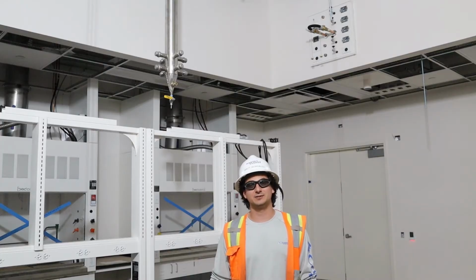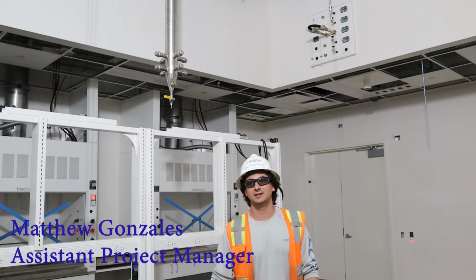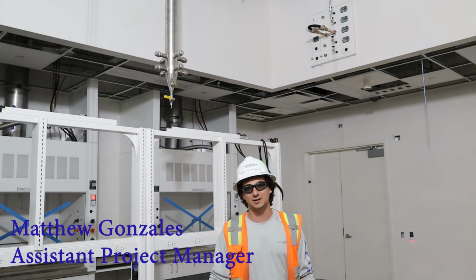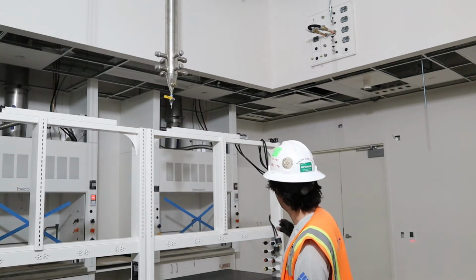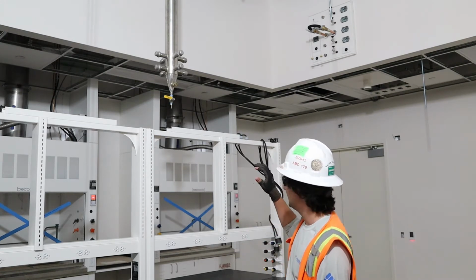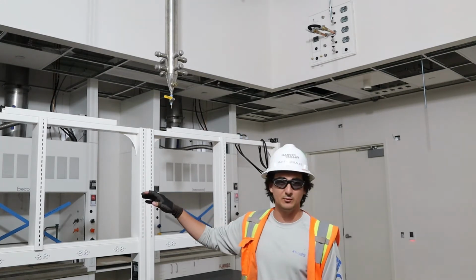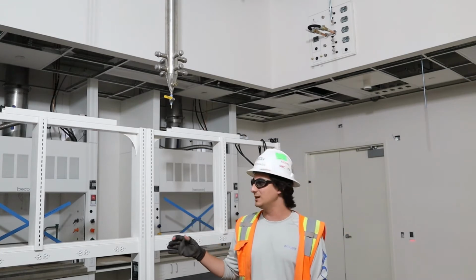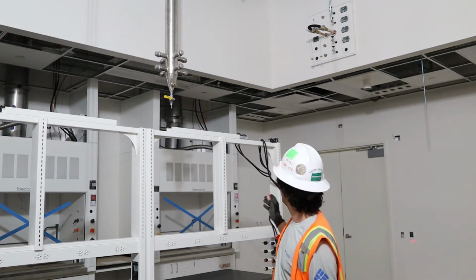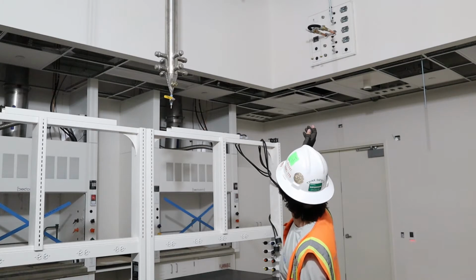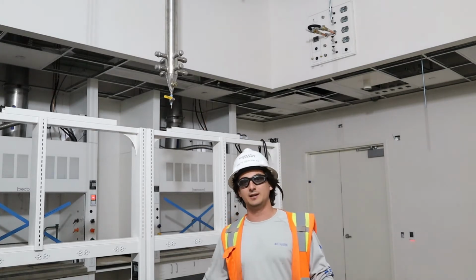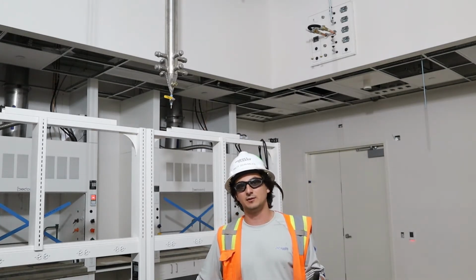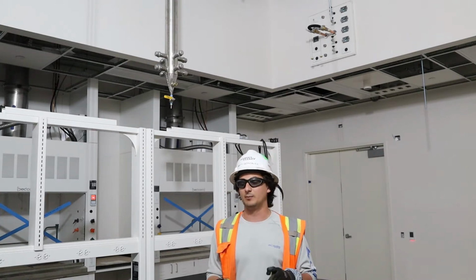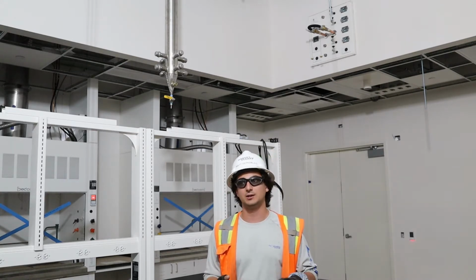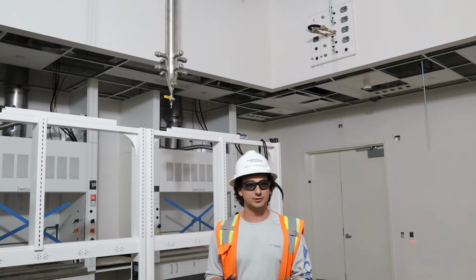Hey guys, Matt Gonzalez, Assistant Project Manager, standing in one of ESC's 52 lab modules. Each lab module has a combination of these worktop benches, fume hoods, some specialty fume hoods like for laminar flow or biosafety. And all these pieces of equipment are fed from ceiling service or wall service panels that house a number of utilities, anything from compressed air, vacuum, compressed nitrogen, compressed argon. They have chill water circulation loops for cooling lab equipment.